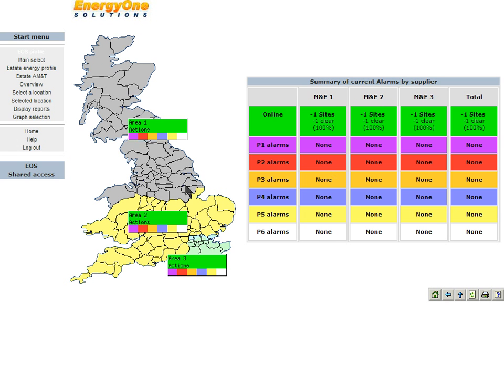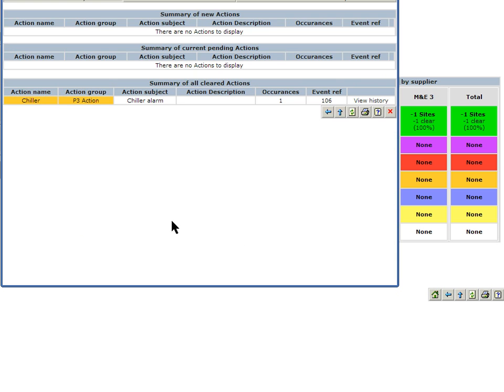There is a color-coded escalating alarm system providing for a message to be sent to the first in line of support. This would probably take the form of a text message being sent to a local or on-site engineer. If there was no response within, say, 2 hours, then the next up the command line would be sent a message or email, and this continues until someone has reacted to the alarm. A full audit trail is kept for later analysis to determine if service levels are being adhered to.